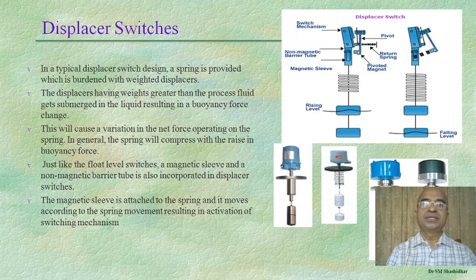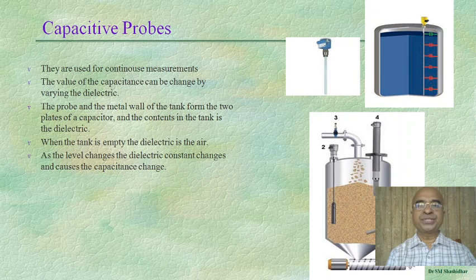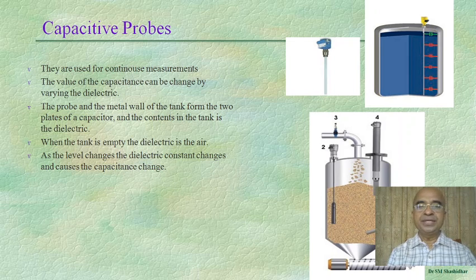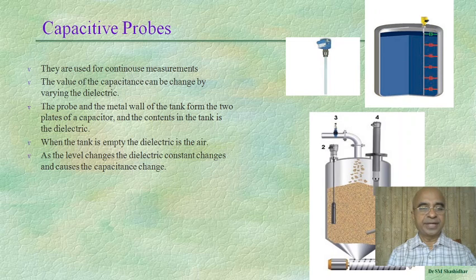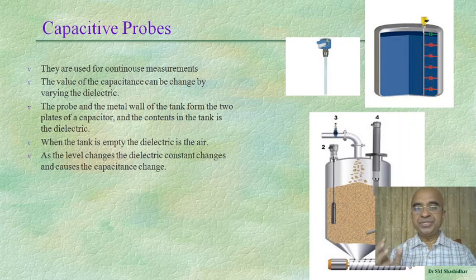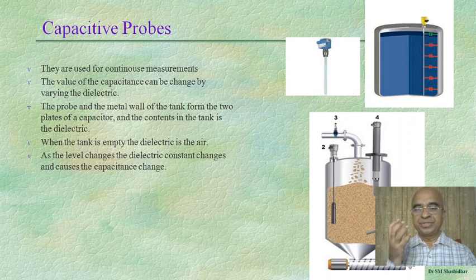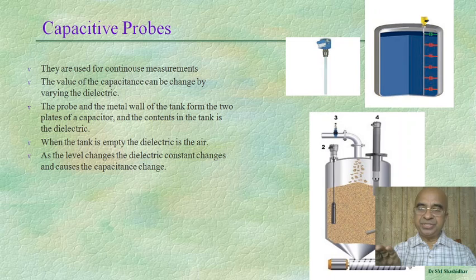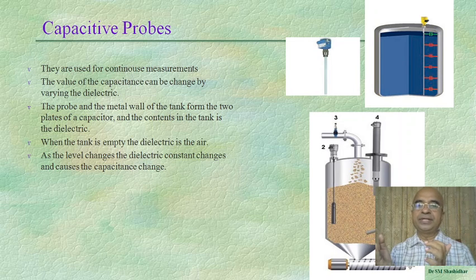Capacitive probes are used for continuous measurements. The value of capacitance can be changed by varying the dielectric. The probe and the metal wall of the tank form the two plates of a capacitor, and the contents of the tank are the dielectric. When the tank is empty, the dielectric is air. As the level changes, the dielectric constant changes and causes a change in capacitance.